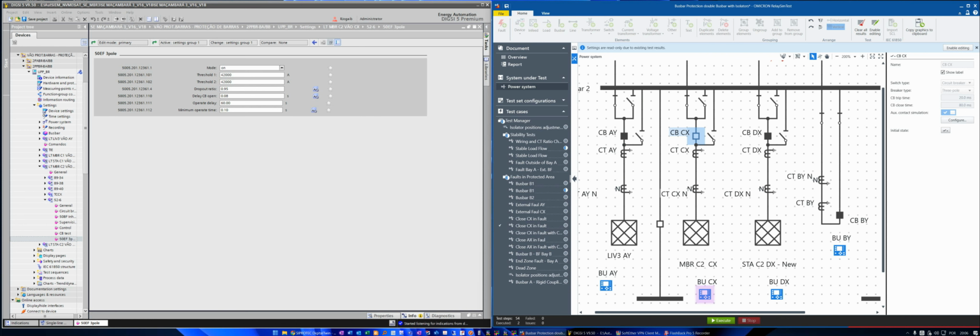We will see first the current flowing in GCT, and after you will see the status of the circuit breaker. So in this case, you have an incorrect operation of the bus bar protection when you close or you do an automatic reclose of this bay in a fault. So the signal of close command, manual or automatic reclose, is important to be put in the signal of the protection.